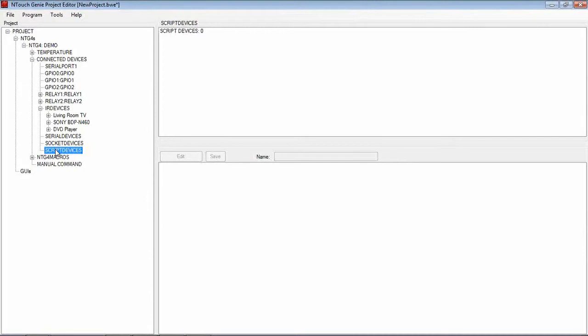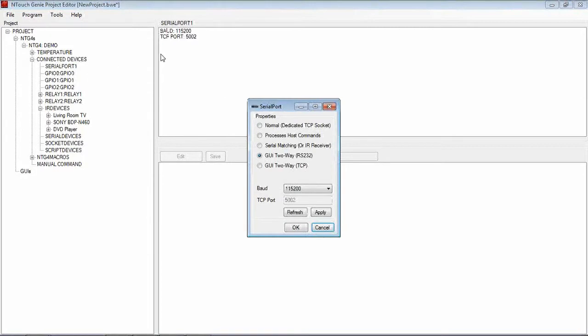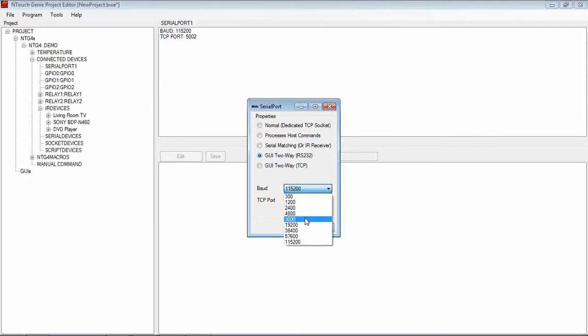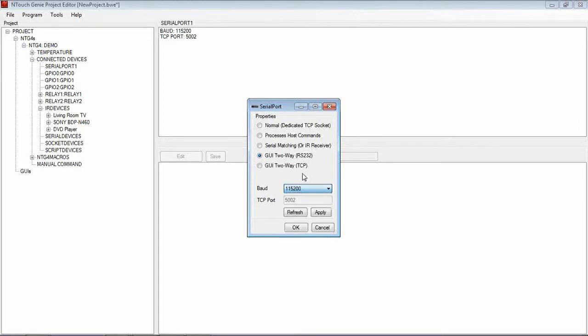Before we have a look at Script Devices, one important thing we need to do is under Serial Port 1, right mouse click on that and go to Properties. Down here we need to set how you want to communicate with your device. Is it going to be RS-232 or TCP? If it's going to be RS-232, you must set the baud rate to match the device, the communication baud speed of the device you want to talk to.